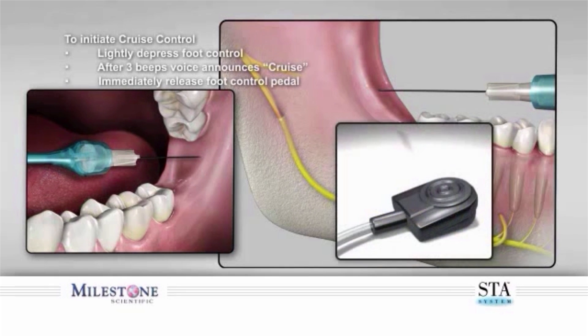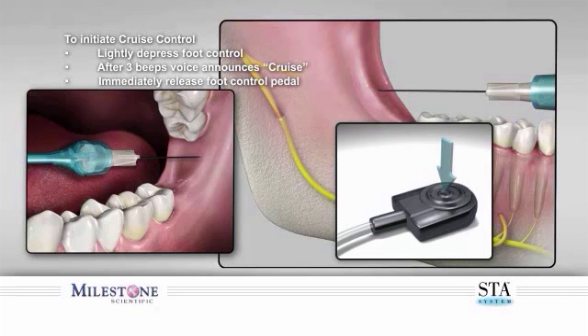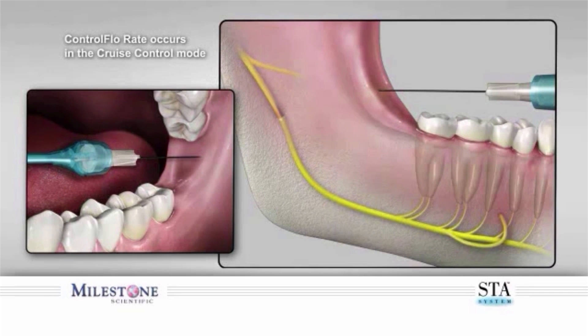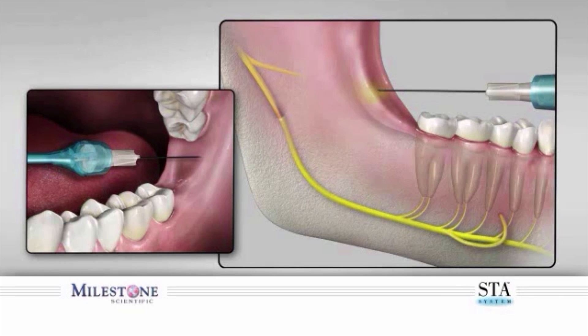After three beeps, you will hear the wand system announce 'cruise.' Immediately release the foot control pedal to enter into the cruise control mode. This allows the controlled flow rate to continue to dispense anesthetic solution, creating an anesthetic zone in front of the tip of the needle. This technique requires a very slow and deliberate needle movement, allowing the anesthetic solution to deliberately precede the path the needle will take.